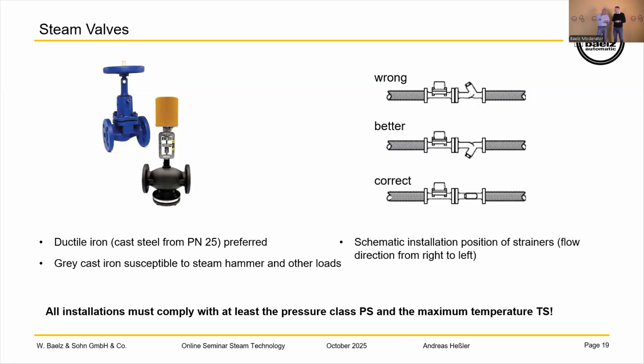When you have just water or very cold condensate, you can of course use the better version. But for steam, it is better to always install horizontally, because the condensate collects on the bottom, and if steam comes together with the condensate, there is hammering, and I have already seen some broken strainers, so it's not nice. Hope this helped.